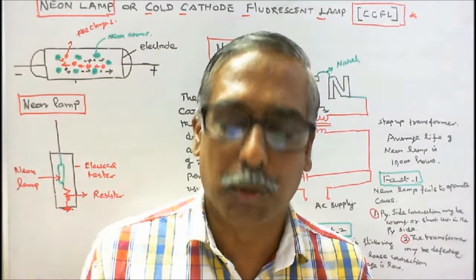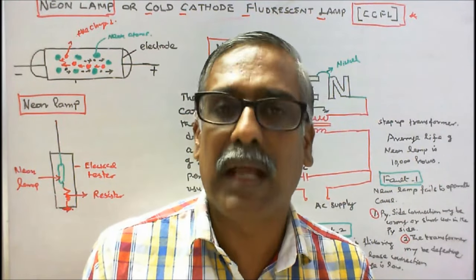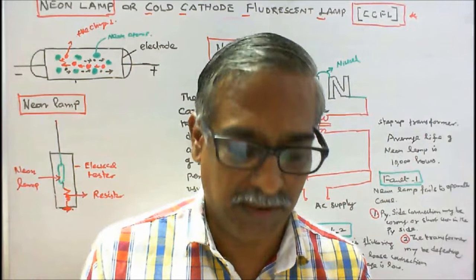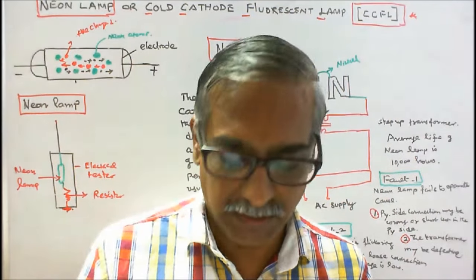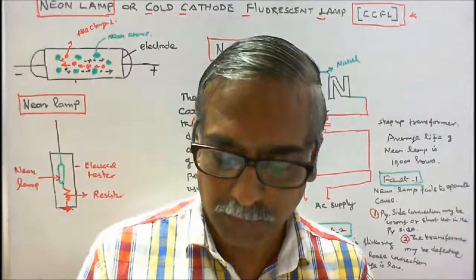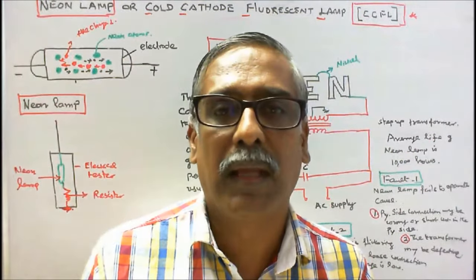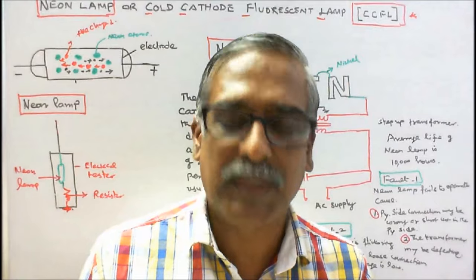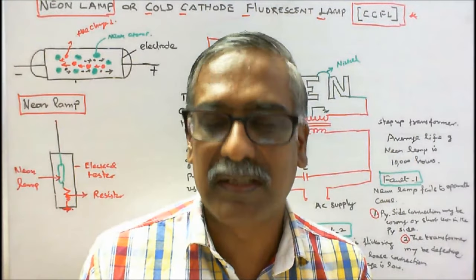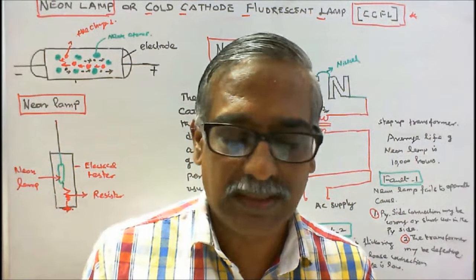The diameter of the tube may be 10, 15, 20, or 30 mm, with currents of 25, 30, 60, and 150 milliamps respectively. The voltage required is 500V to 1000V per meter of tube length. For starting, the neon tube requires twice its operating voltage. Capacitors are used to improve the power factor. The transformer capacity should be 50 to 100 VA. The transformer is made in a special manner with a magnetic shunt, because as the tube warms up its resistance decreases and the current increases, which a simple transformer cannot handle.